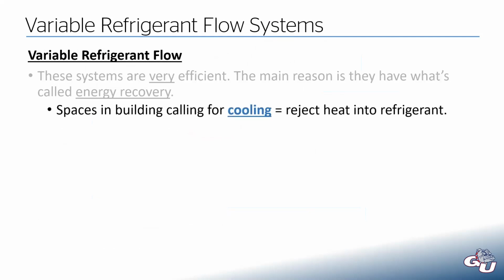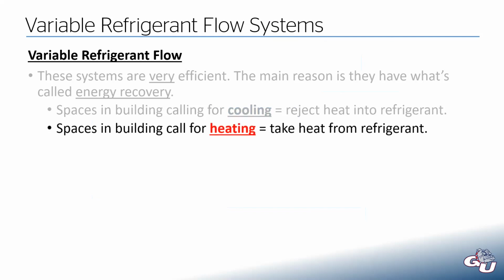So we are going to have some spaces in our building that are going to be calling for cooling. Any one of those fan coils that is in cooling mode, they are taking heat out of the space and then rejecting that heat into the refrigerant, which then goes into the overall network. And you could have some other spaces in your building that are calling for heat. So this could be, maybe it's a moderately cold day, but you have a conference room in the middle of your building that is chock full of people. That conference room is still going to need cooling, even if other spaces need heating because it is a cold day. Any of those rooms that are calling for heat, they're going to be taking heat out of the refrigerant and then delivering it into the space.